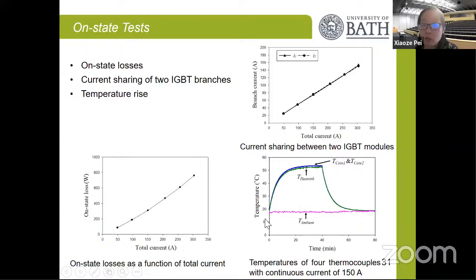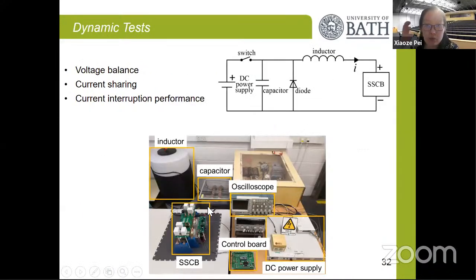But what we can say here is, with only a solid state circuit breaker carrying 150 amps, the temperature rises from 20 degrees centigrade up to 50, and then it's pretty much stabilized. So we can say the losses of the solid state circuit breaker are still quite high. That is the main reason the hybrid circuit breaker is mainly used.